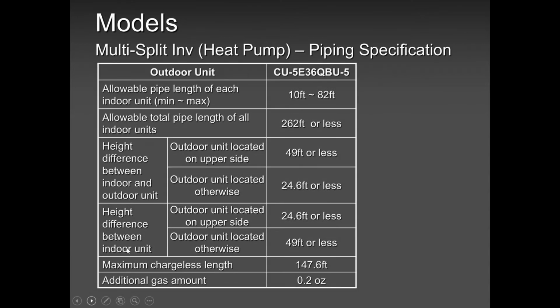Then obviously, you need to focus on pipe lengths, especially when you're doing a multi-zone. It could be a big house. It could be longer pipe lengths. So always remember to obey the pipe length. Okay, guys? For this case, for this 5 zone, maximum pipe length is 82 feet per indoor unit. Total pipe length is 262. Height difference is 49. And if the outer unit was located otherwise, lower or in the middle is 24 feet.